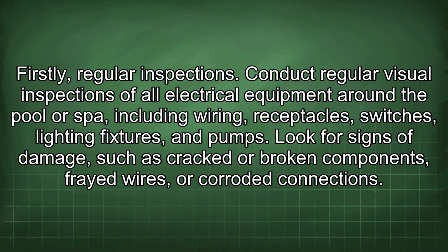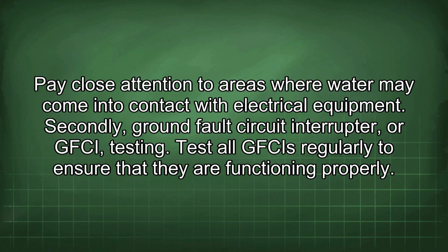Firstly, regular inspections. Conduct regular visual inspections of all electrical equipment around the pool or spa, including wiring, receptacles, switches, lighting fixtures, and pumps. Look for signs of damage such as cracked or broken components, frayed wires, or corroded connections. Pay close attention to areas where water may come into contact with electrical equipment.